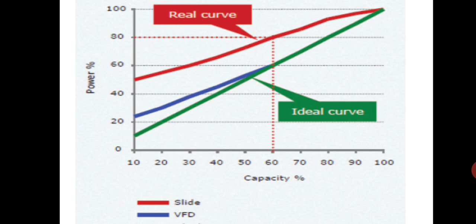the capacity reduces, instead of 100%, suppose you are running at 60%, you can see the real curve power requirement is very high, 80%. Whereas if you use a VFD, you can run it with 60% of power. So you are almost saving 20% of the power. So this is of great help. Like I can give one example in a lift. Suppose a lift is designed for 500 kg, and only one person is traveling. In this case, these are helpful in conserving the energy.